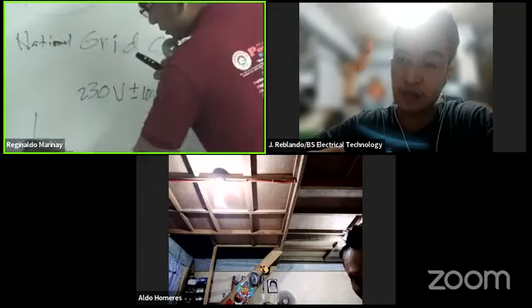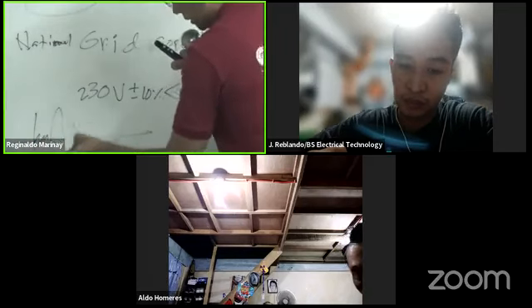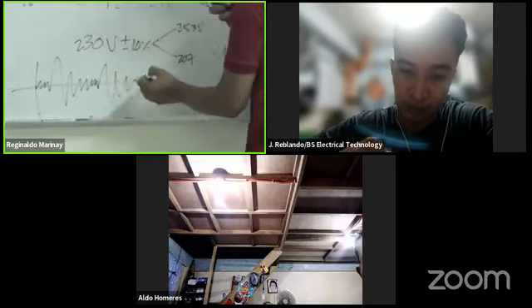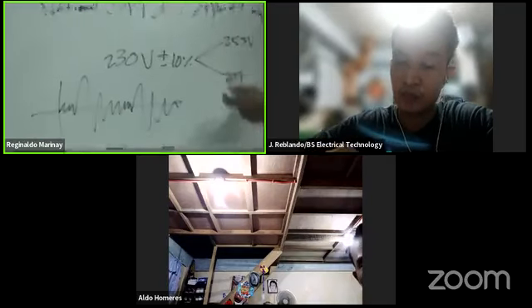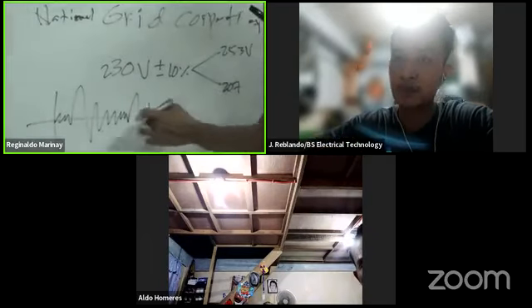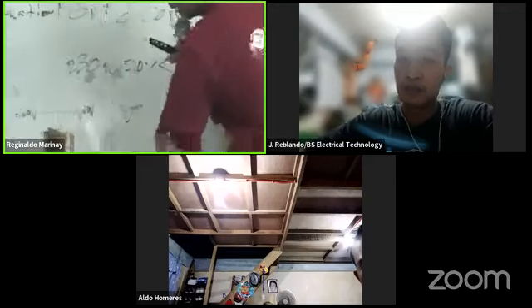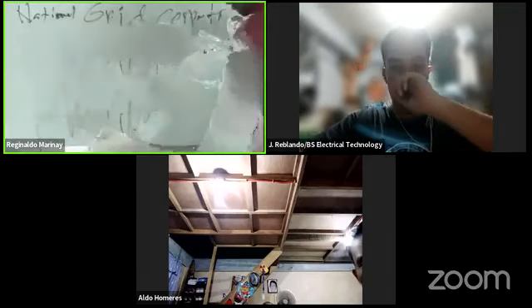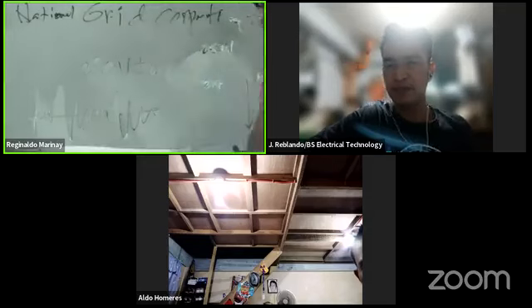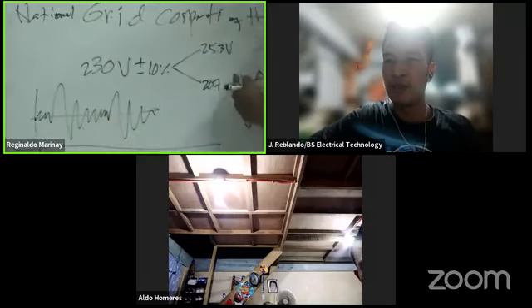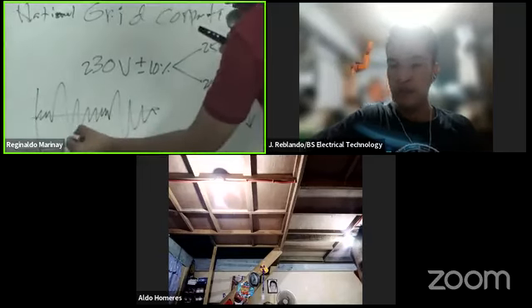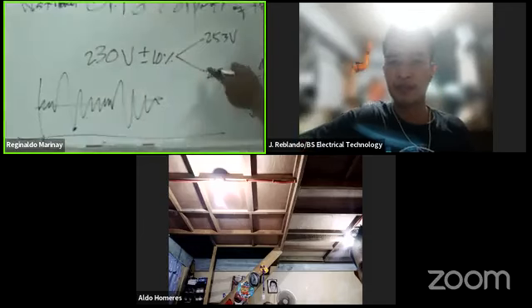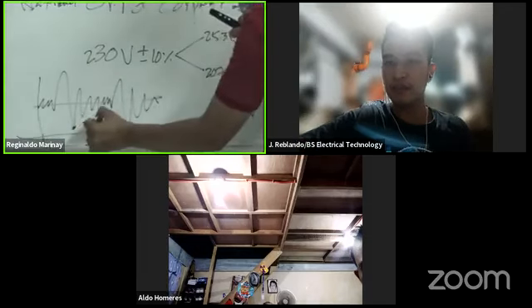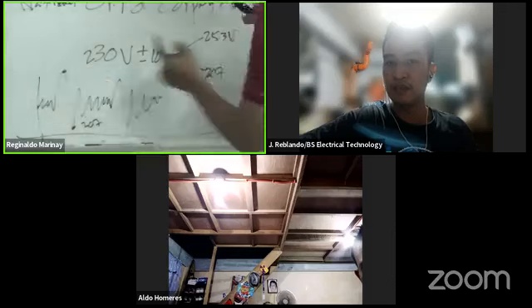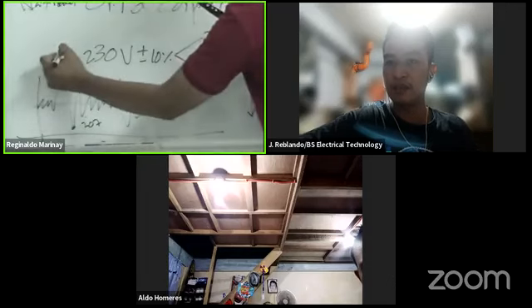This means the fluctuation in the voltage must range from 207 to 253—sorry, we should not include beyond that. So let's say this shows the fluctuation of these voltages. The lowest point should be 207, and the highest should only be 253.